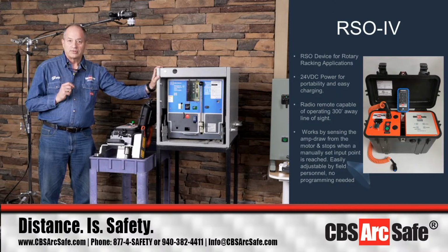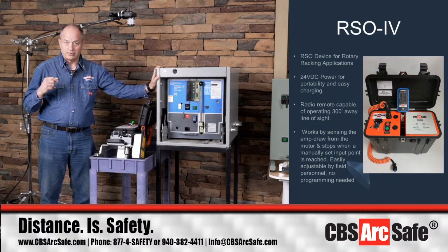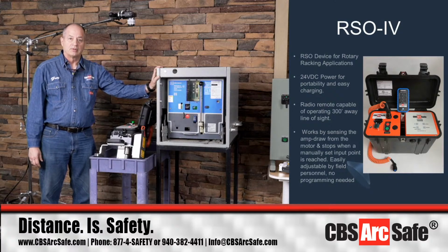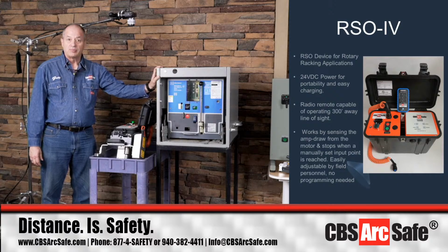So we had to work to determine that through the use of torque wrenches and looking at tools and figuring this stuff out for ourselves. We built our tables so we knew what acceptable torque levels were based on the manufacturer, the amp frame size, and the mass of the breaker. Those are the variables that help us determine how much force it should take to rack your breakers.